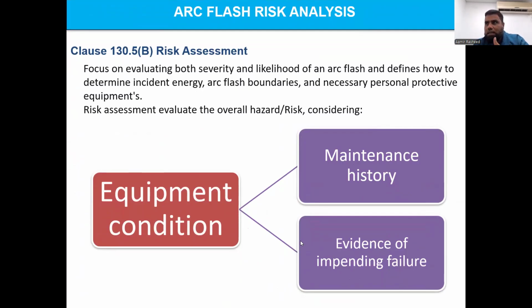Severity is influenced by the incident energy, and likelihood depends upon the task, how often you are performing the task, the condition of the equipment, and the maintenance history. So that comes to the risk assessment. NFPA 70E requires that arc flash studies and assessments must be reviewed at least every 5 years, because conditions change, legal requirements change, and operational things change.